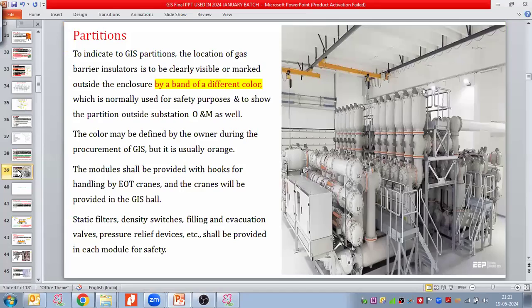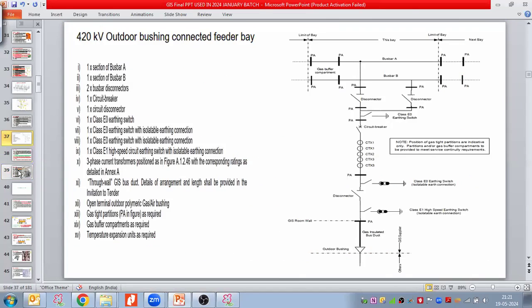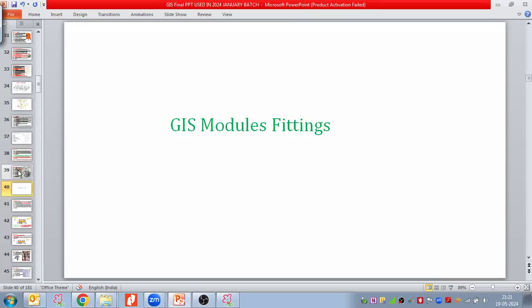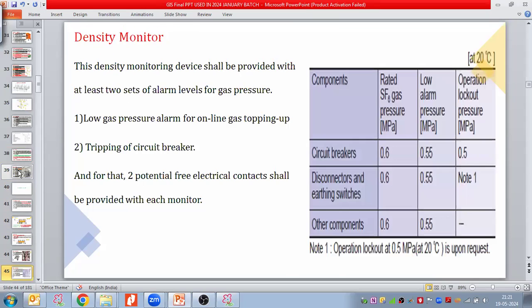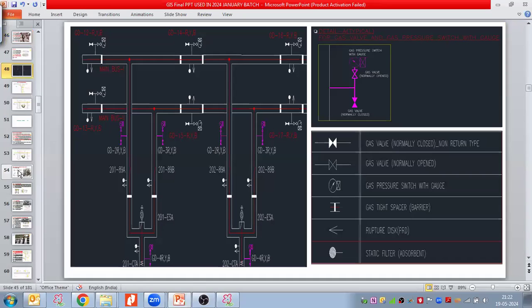fittings. So as a design engineer, when you are working on a GIS type substation project, you have to ask the GIS manufacturer for the gas SLD, and then you have to review how the partitions are made and what kind of fittings they have provided, and whether this is as per the technical specifications and the requirement or not. We discussed all this practice yesterday, so you can take that as a reference, right?